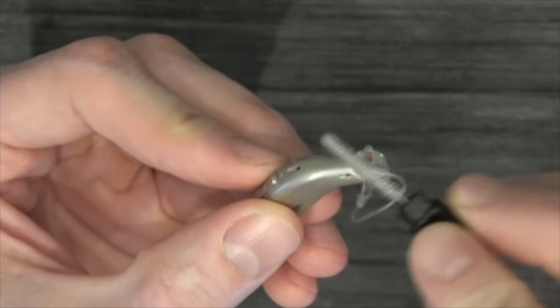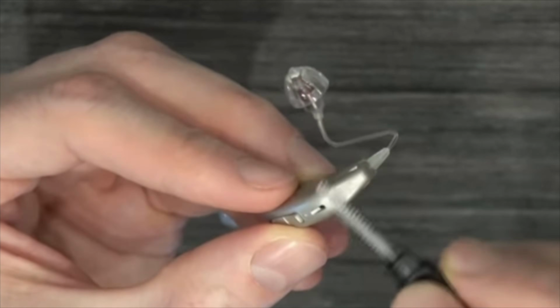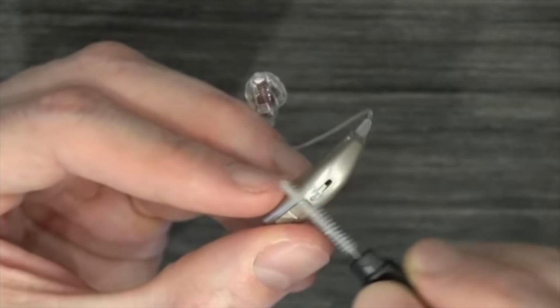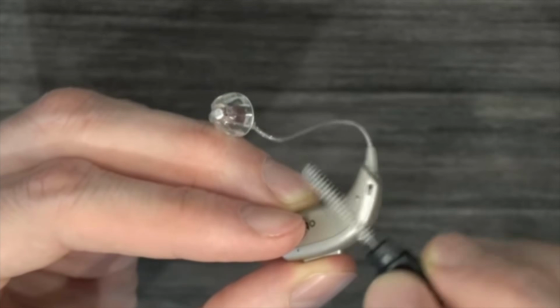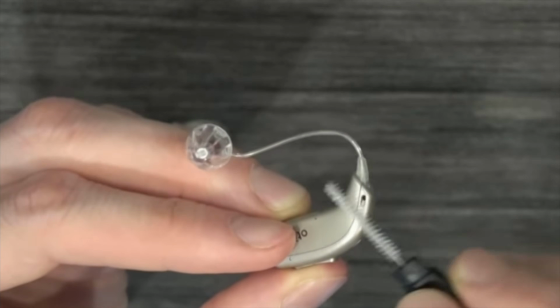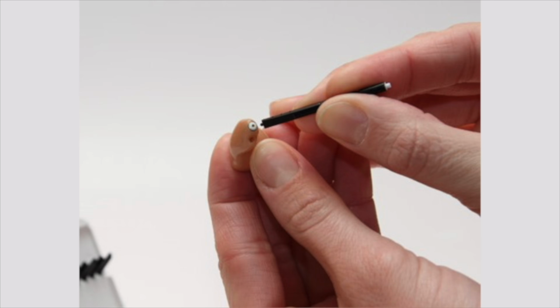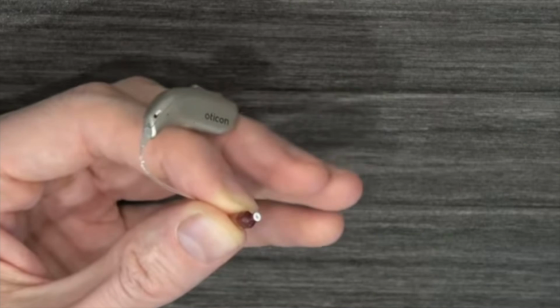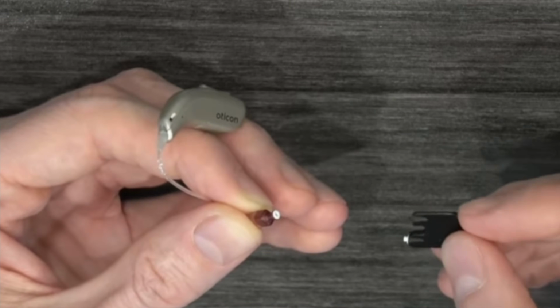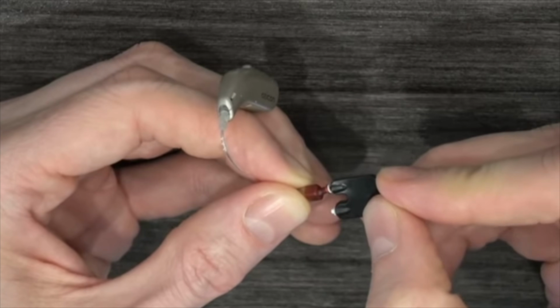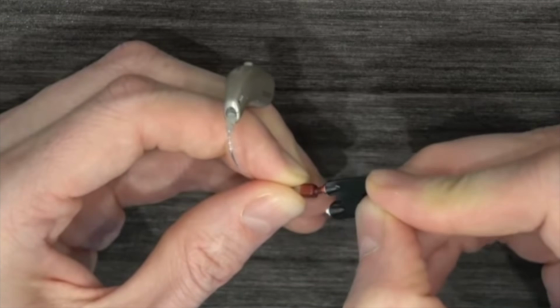Using a gentle amount of pressure, lightly brushing the microphones helps to remove buildup from hair products, skin oil, dust, and sweat. Most hearing aids also have a wax guard or wax filter that's located at the end of the receiver wire, ear mold, or body of a custom hearing aid. If wax accumulates in the wax guard, the sound from the hearing aid is weakened significantly, and it may even sound like the hearing aid is completely dead.